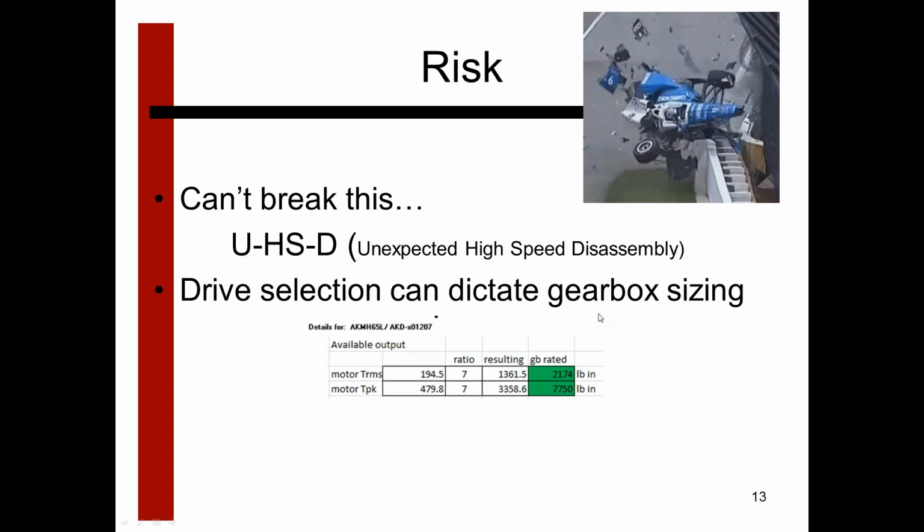Oftentimes, when I've zeroed in on the drive and the motor now, it's typical that I did not need full current output from that drive for that particular application. But I'll go ahead and make the next step. I will apply full torque, which is full current out of the drive, into the motor, and then carry that through the rest of the mechanics and see if there's anything that is exceeding a limit. So down below, I tend to highlight my boxes in green if things are good.